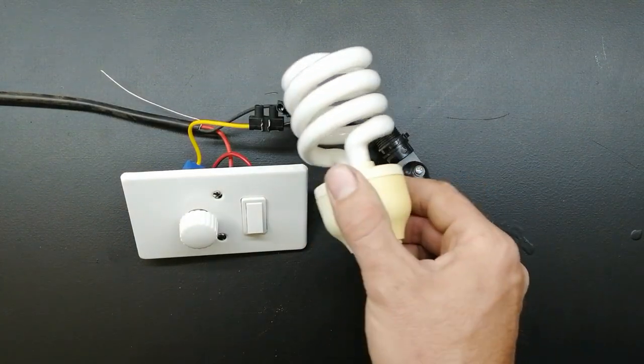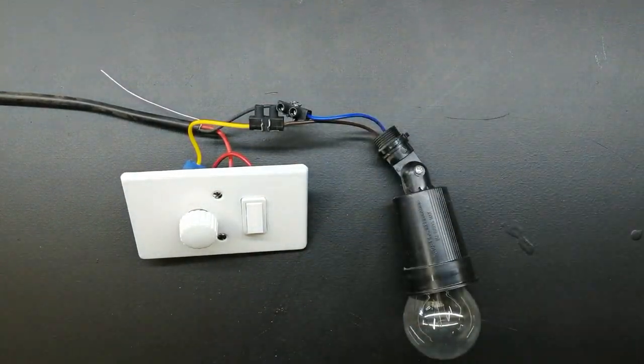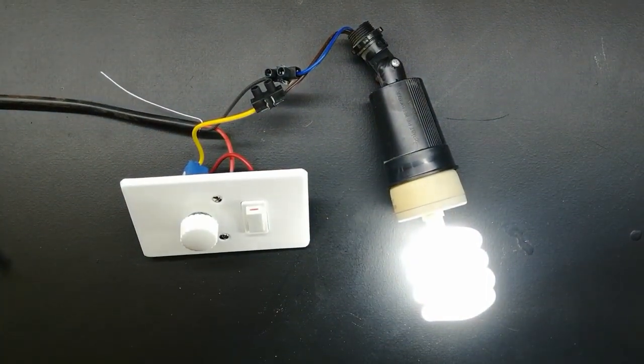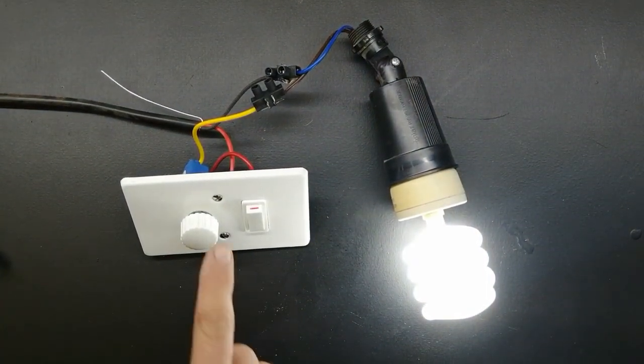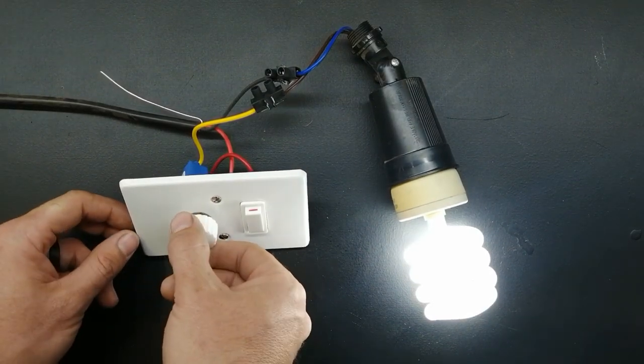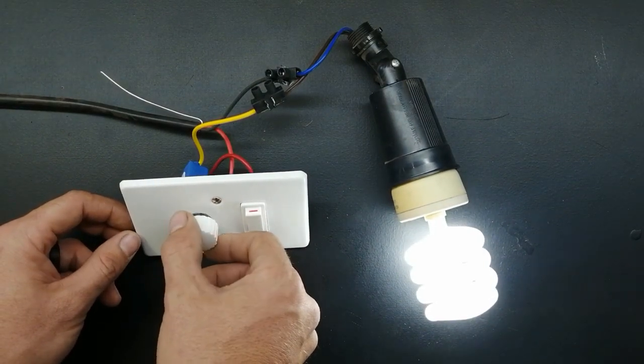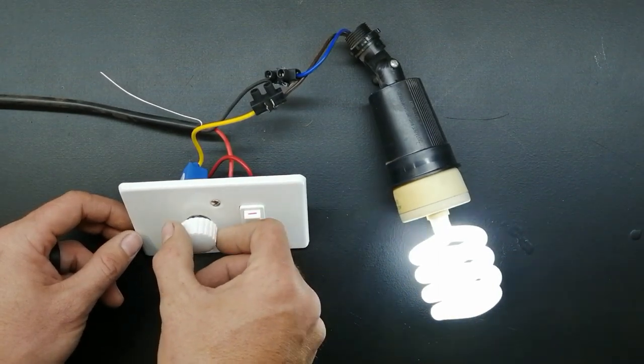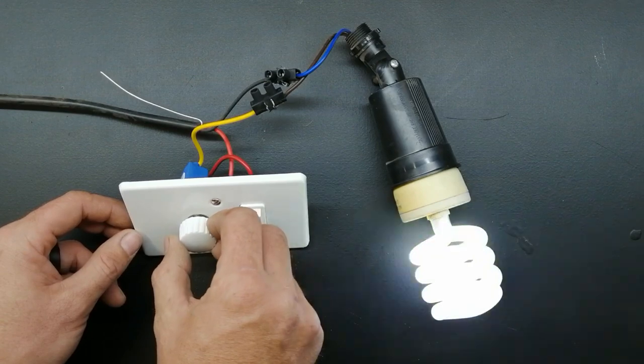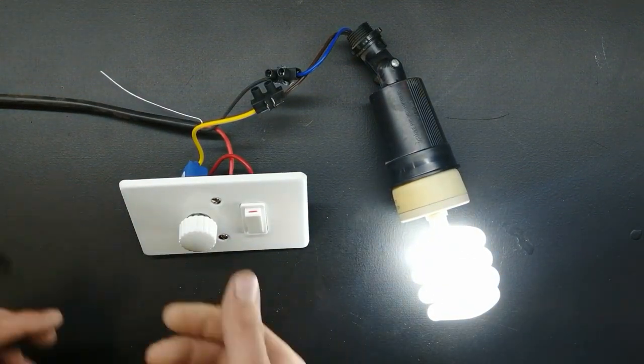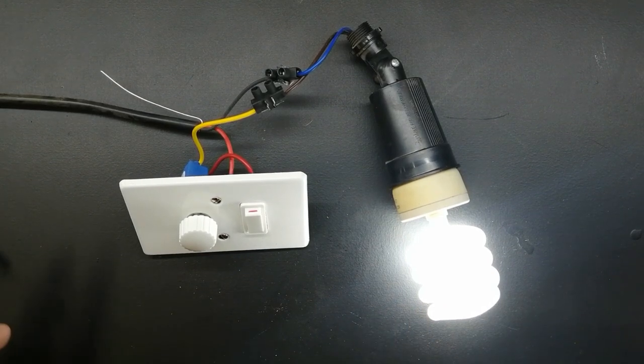I'm going to show you why you can't use one of these fluorescent fittings. Let's see what happens when I put one in. It works fine when you've got the dimmer cranked up all the way, but as soon as you start dimming the switch, you can see it starts flickering. It doesn't want that dimmer on there. You put it up all the way, it's fine. Start dimming it, it starts to flicker.